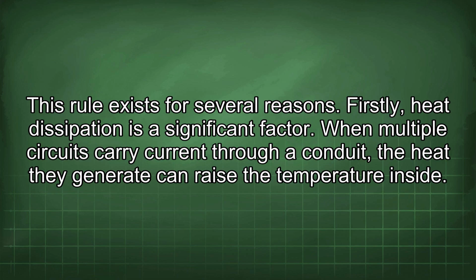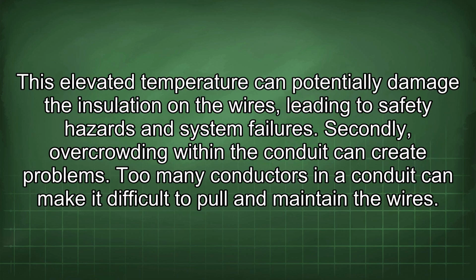Firstly, heat dissipation is a significant factor. When multiple circuits carry current through a conduit, the heat they generate can raise the temperature inside. This elevated temperature can potentially damage the insulation on the wires, leading to safety hazards and system failures.